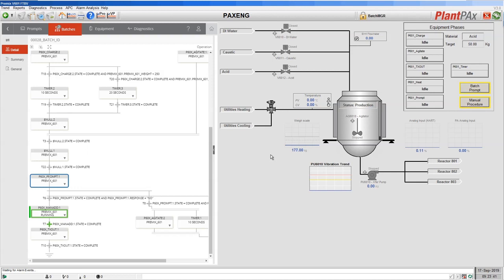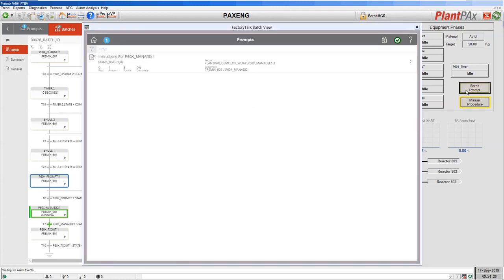So far in this demonstration, every equipment phase that we've been running — each of those processing steps — has been an automated step. It's had automated valves, pumps and motors being controlled by a PLC or DCS controller. FactoryTalk Batch has been starting and stopping them in those controllers as required with their required values. But FactoryTalk Batch can also support manual procedures. This feature is called eProcedure. Here we have a manual procedure that the operator needs to execute, and again we can see a prompt asking us to respond. We can see that we now have some instructions that we need to follow as a prompt.